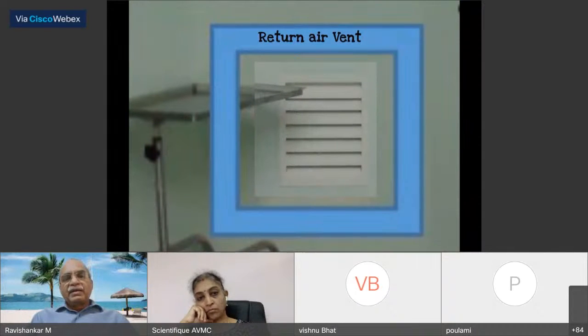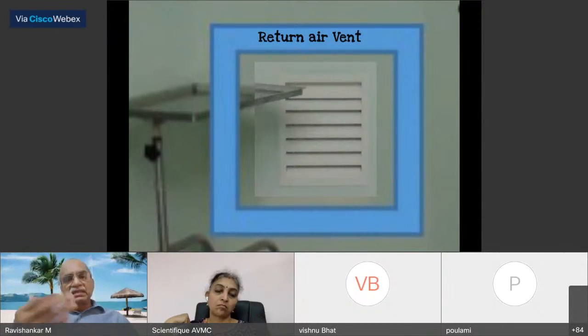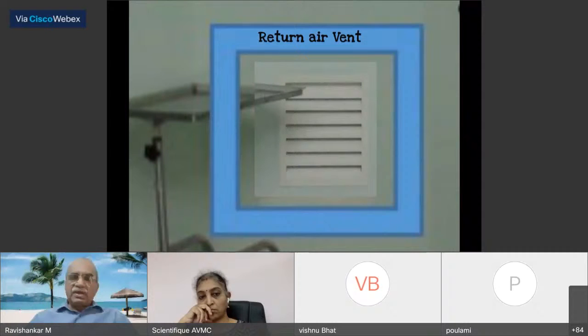And then it is returned back. The return air goes from the four corners of the operation theater, so the flow becomes laminar. The return is at the bottom of the theater, not at the top. It flows from the top and goes down to the bottom.